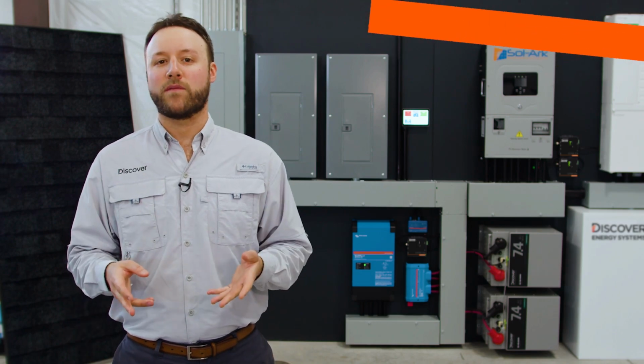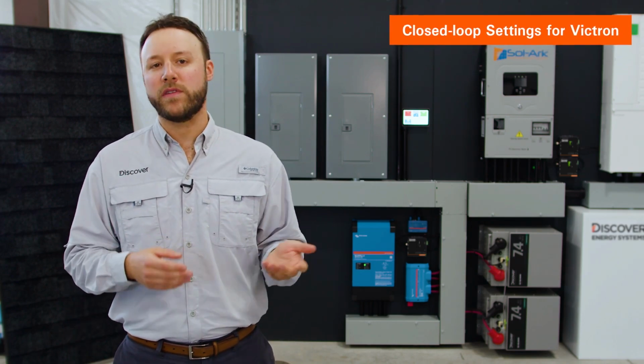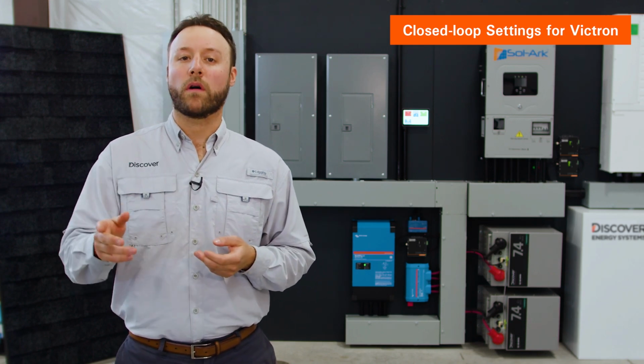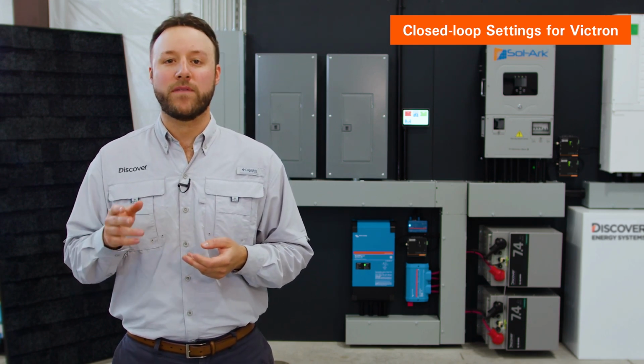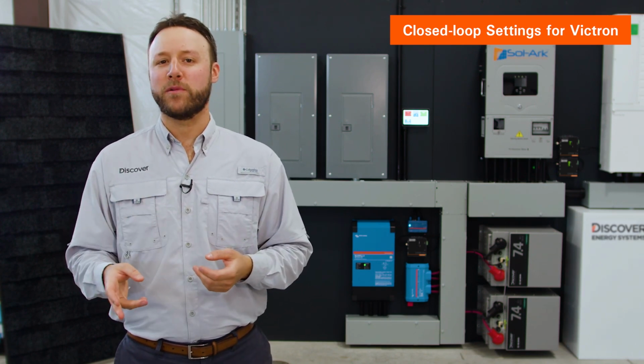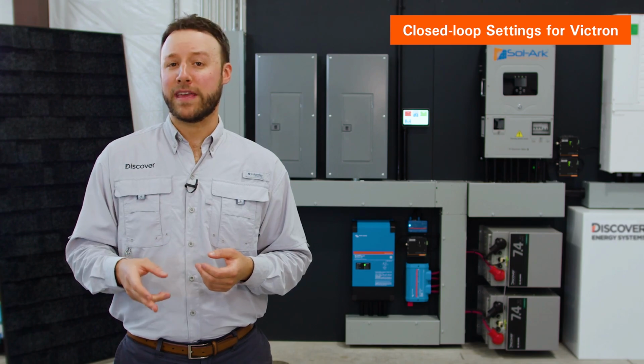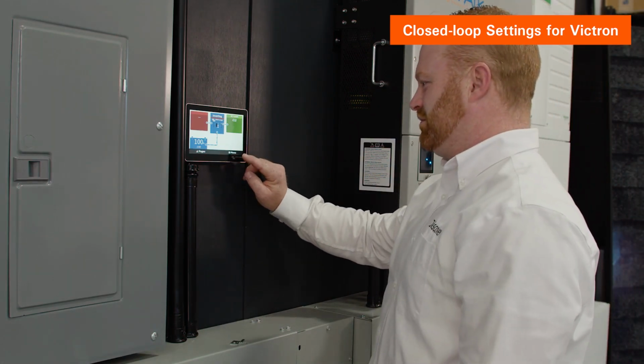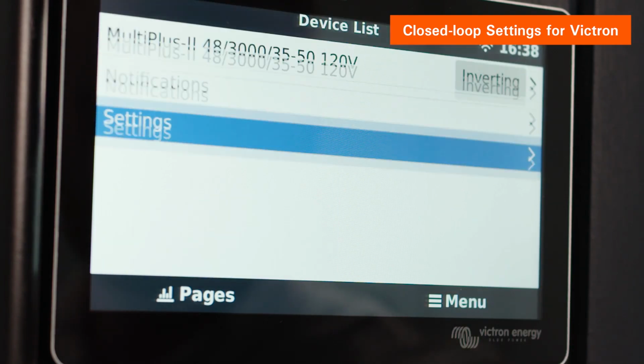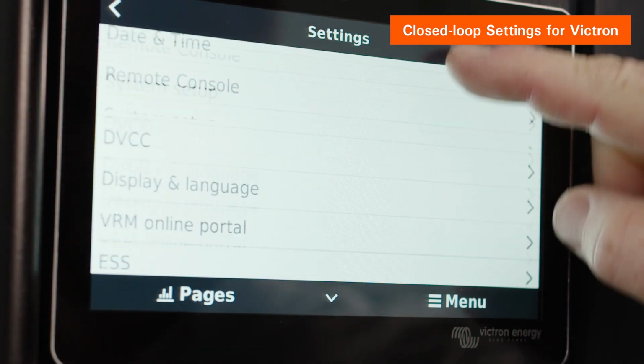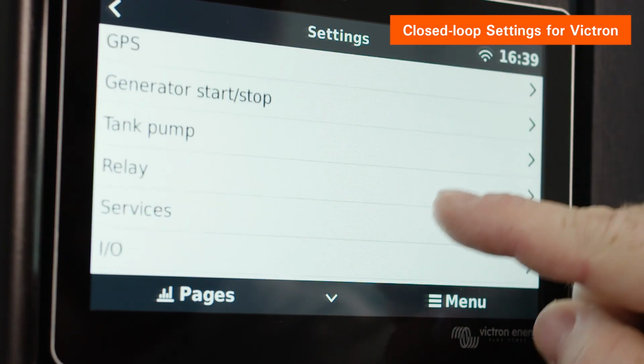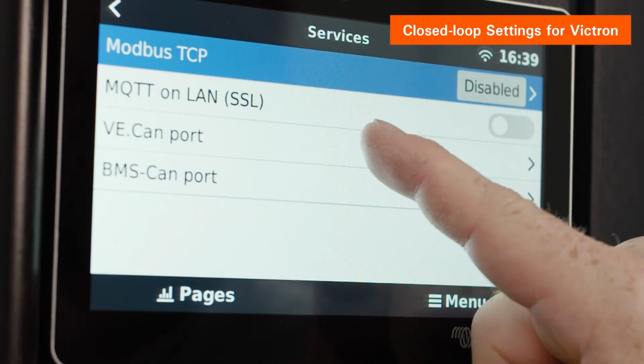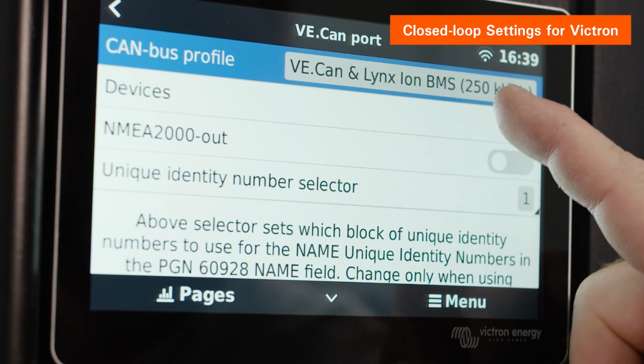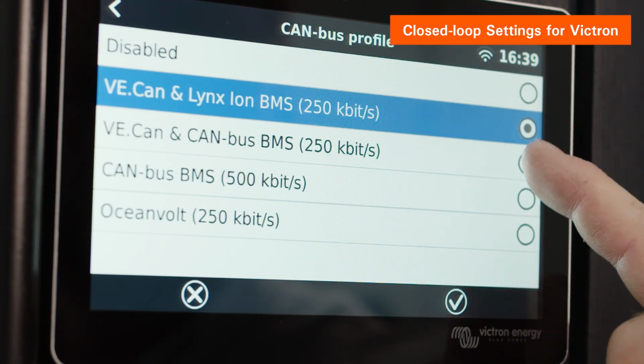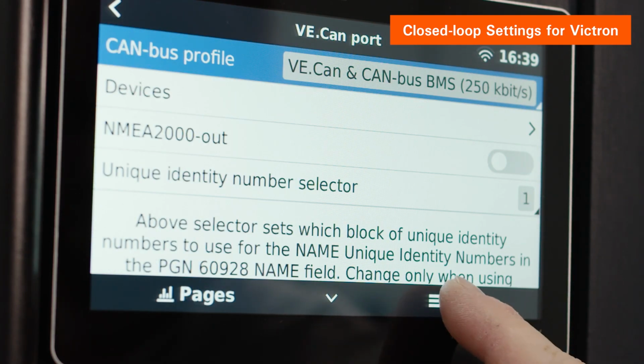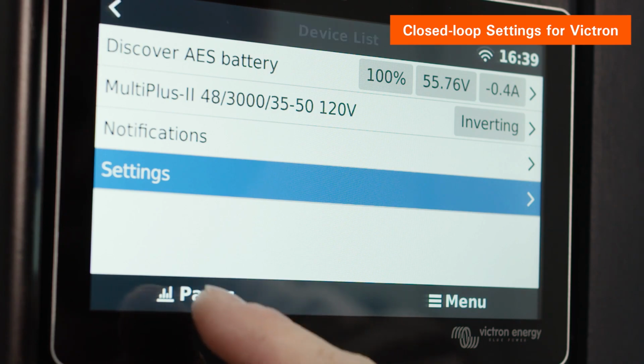Now let's program the Victron inverter charger with closed-loop parameters using the Victron CCGX device or remote console via the Victron VRM portal. First, enable communication with the Discover Lithium batteries by setting the communication speed. Using the CCGX or remote console, navigate from the device list to Settings, to Services, VE CAN port, CAN bus profile, select VE Can and Lynx Ion BMS. Return to the device list and the Discover Lithium battery should now appear.